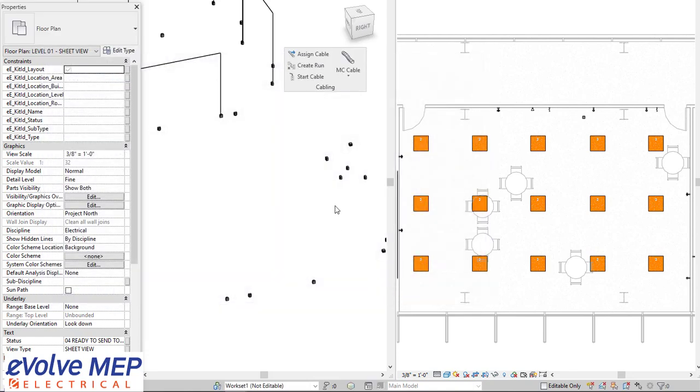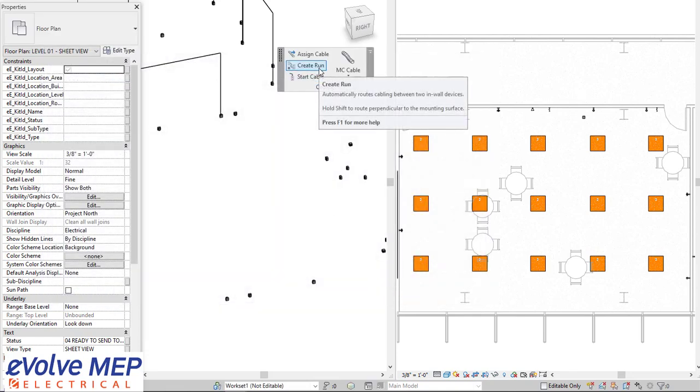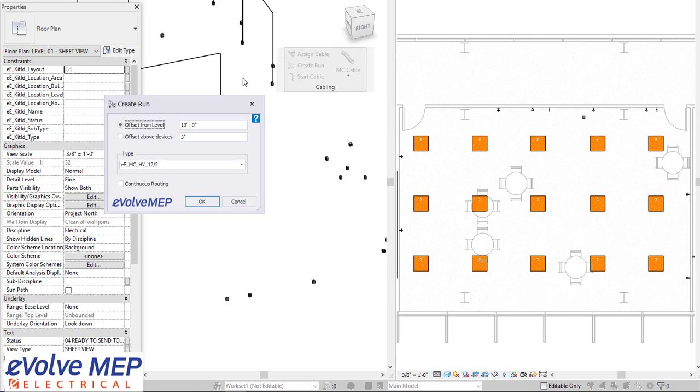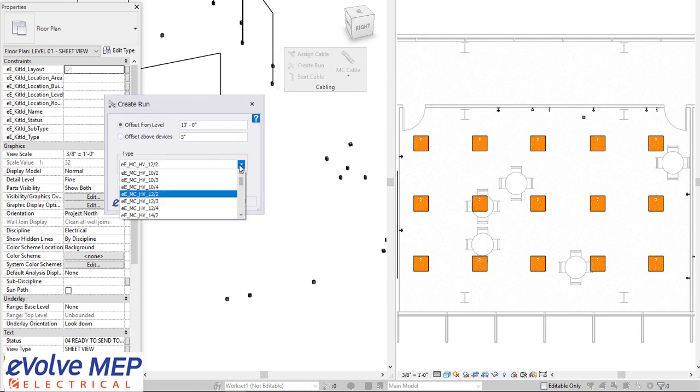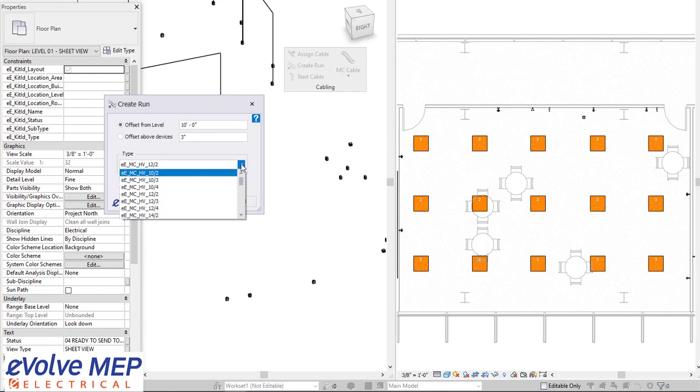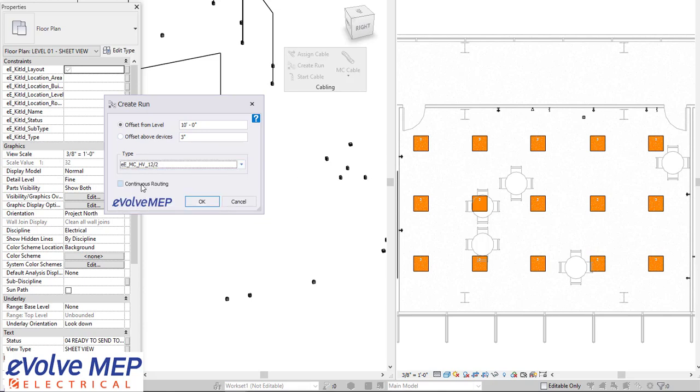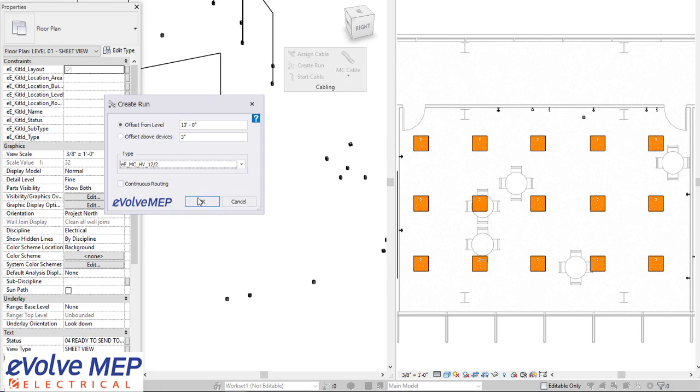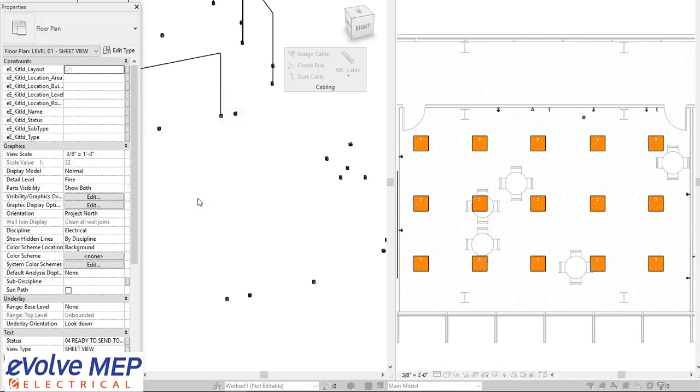So then we have our start cable or create a run. I'm going to first show you our create run. We have our offset from level, offset above device, and we also have the ability to choose all the different types. You're going to do continuous routing, which allows you to continue to select your devices and route them together instead of having the dialog box keep popping up.